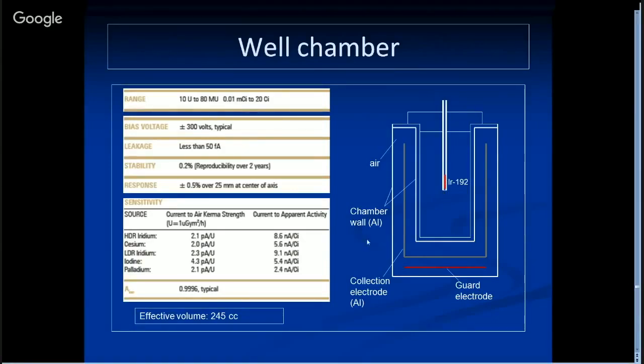You need to do temperature and pressure correction. First, you need to make sure the well chamber is in the range of the source activity, and that the ion chamber is stable and the response is correct, sensitive enough to detect the radiation.